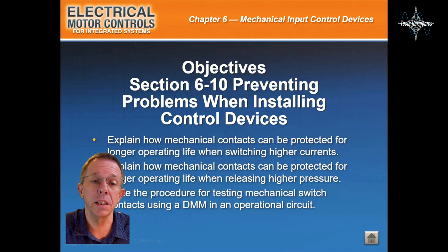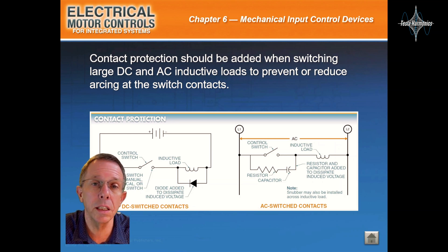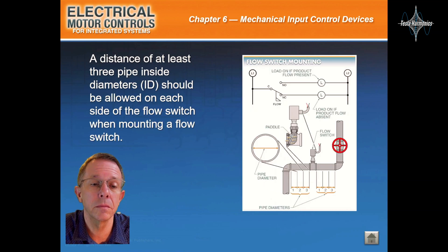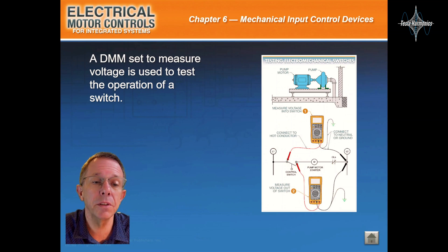Section 6-10: Preventing Problems When Installing Control Devices. Contact protection should be added when switching large DC and AC inductive loads to prevent or reduce arcing on switch contacts. A pressure relief valve may be added to a circuit to protect a pressure switch from excessive pressure. A distance of at least three pipe inside diameters should be allowed on each side of the flow switch when mounting it. A DMM set to measure voltage is used to test the operation of the switch.